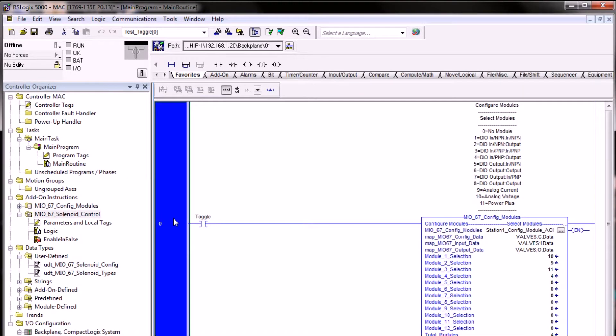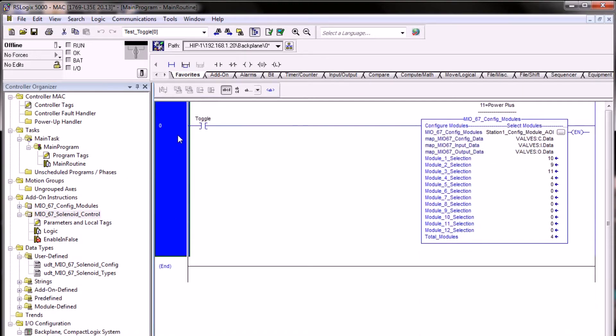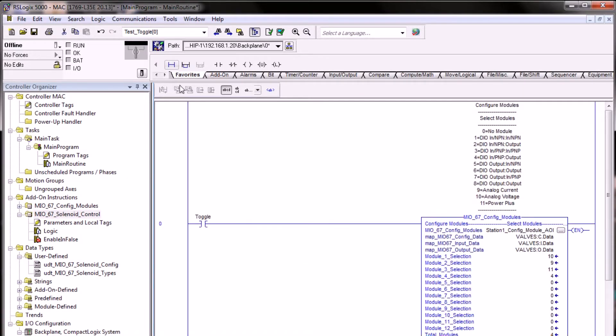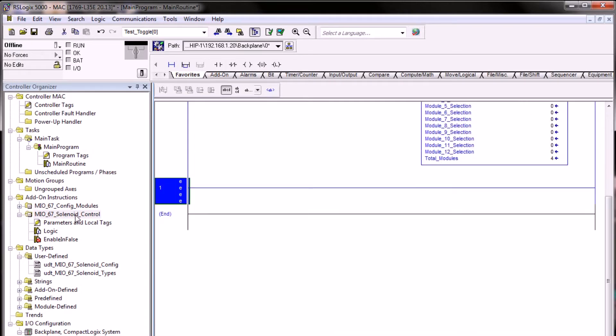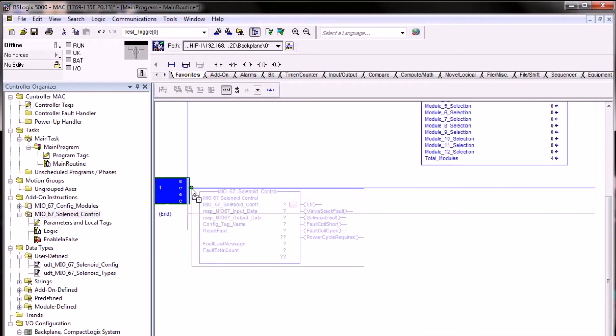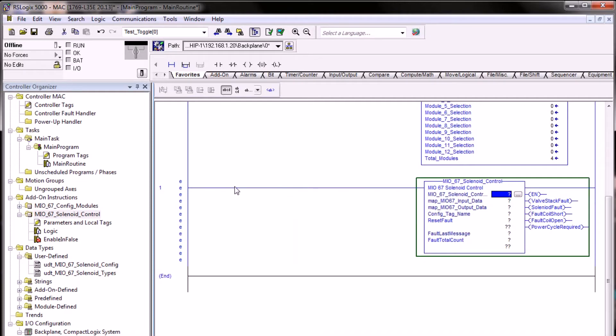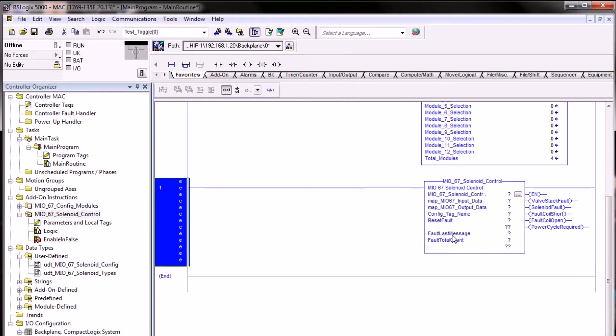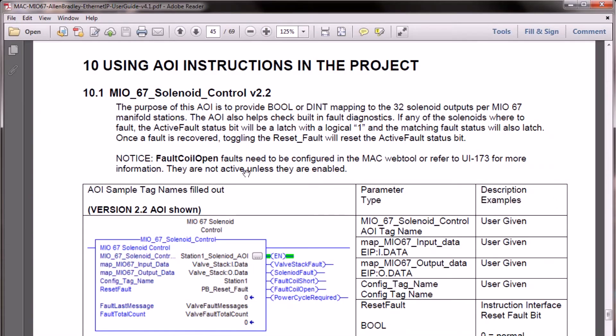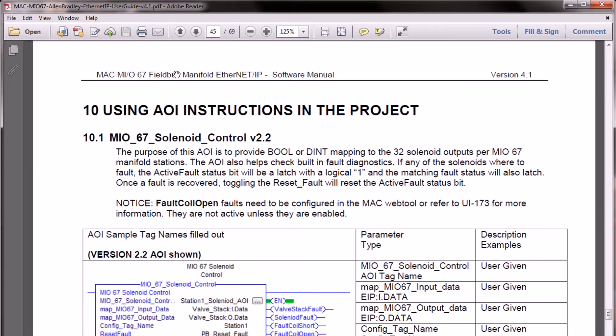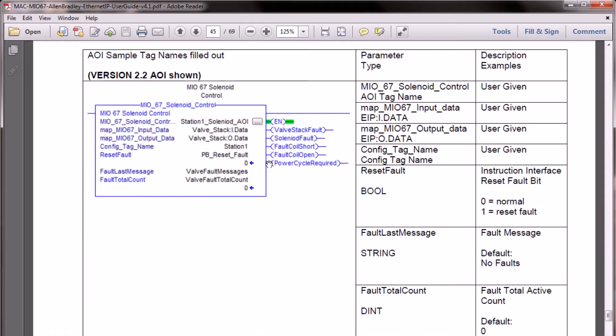Once the AOI is imported we will need to create a new rung for it. We can drag and drop the AOI onto the rung here to create an instance of it. If we're not familiar with the settings we need to configure for the front panel of the solenoid control, we can refer to the manual provided as a PDF file, the Fieldbus Manifold Ethernet IP Software Manual version 4.1. Inside here there is always a table that describes the parameter type and data type configuration required for each of the input or output instances.